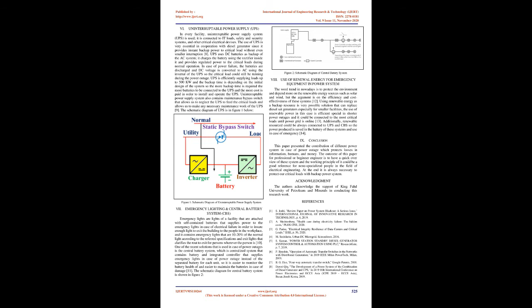UPS uses DC batteries as backup of the AC system. It charges the battery using the rectifier inside it and provides regulated power to the critical loads during normal operation. In case of power failure, the batteries are discharged and the DC voltage is converted to AC using the inverter of the UPS, so the critical load can still run during the power outage.